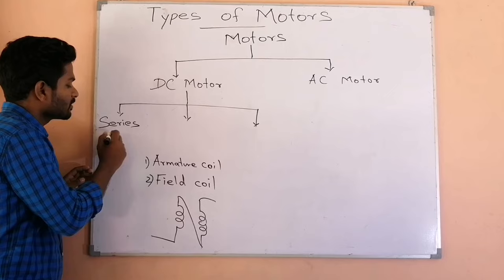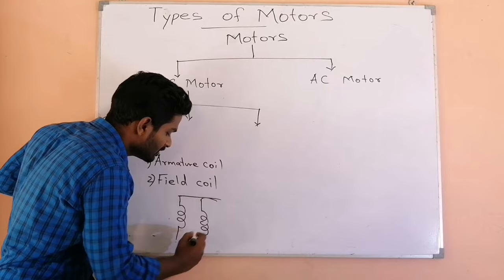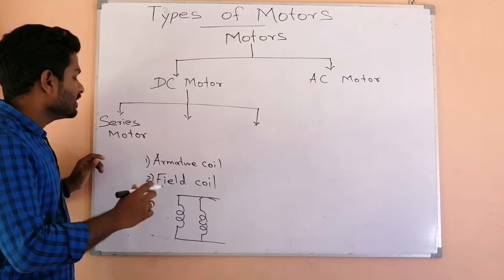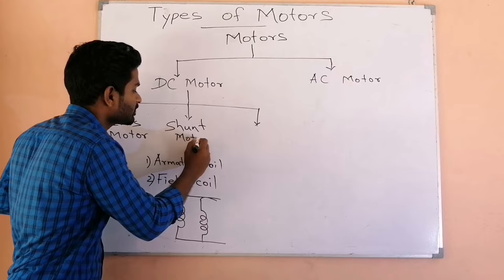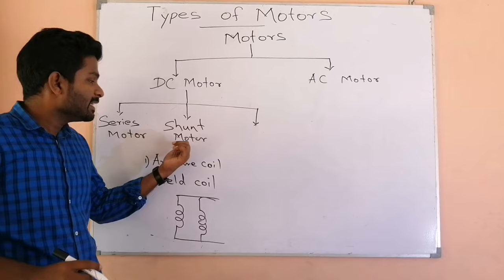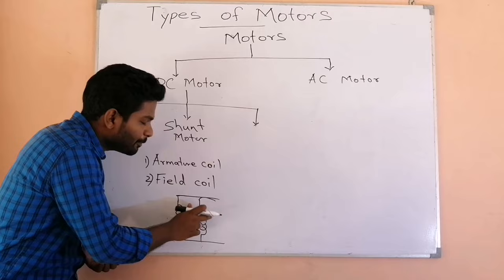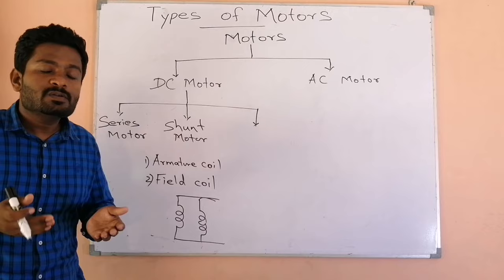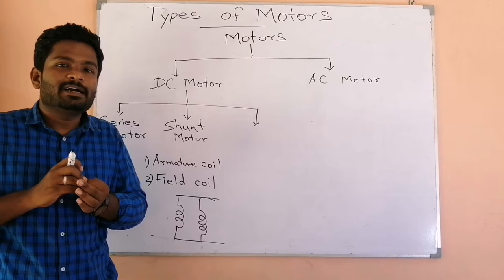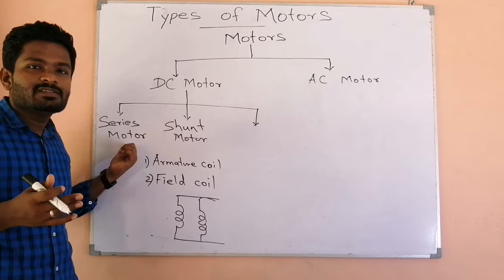One way of connecting the two coils is a series connection — when both coils are connected in series, that type of motor is called a series motor. Another way is a parallel connection — when both coils are connected in parallel, that kind of motor is called a shunt motor. When connected in series or parallel, the motor shows different characteristics in terms of torque and speed.